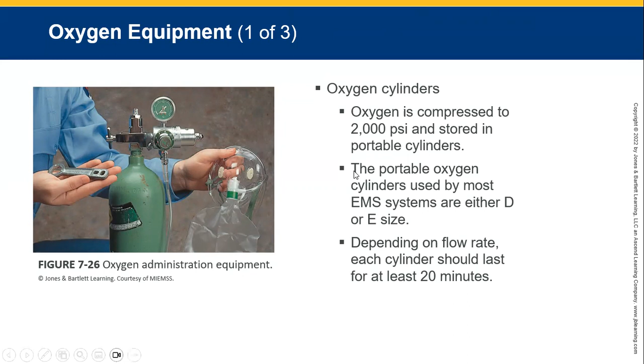If we take a look at the top of this portable cylinder, we will see that it has a regulator or flow meter. These are attached to the cylinder. They have 2 indexing pins and a rubber O-ring. When we've thumb tightened the regulator in the correct place, we can open the flow rate of the regulator, from half a liter per minute, to 2 liters per minute, up to 15 liters per minute. The O-ring gasket supplies a good tight seal. Before we open the actual tap, we're going to open the regulator on the side, 1 or 2 is quite enough, and then we open the tap on top.